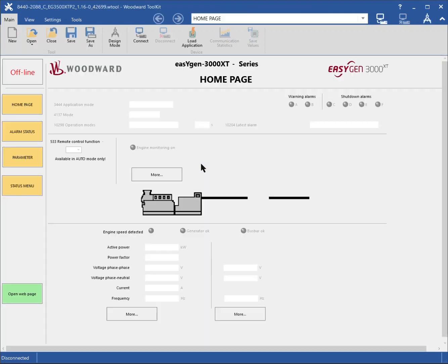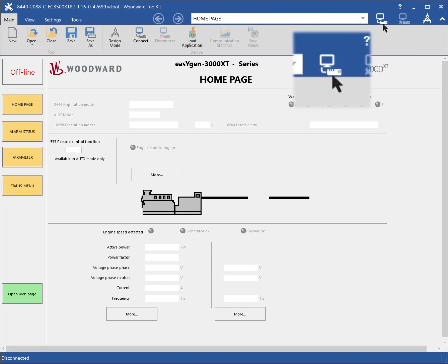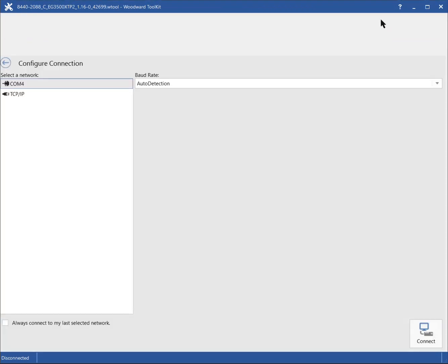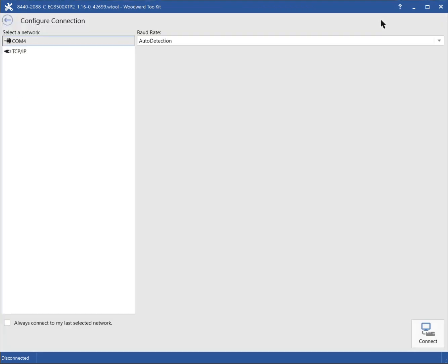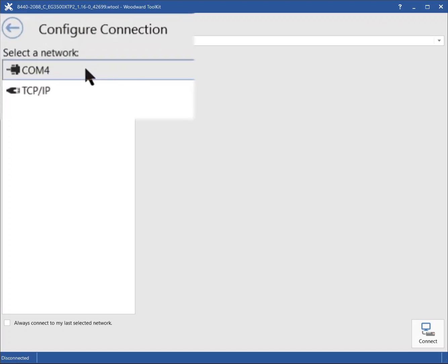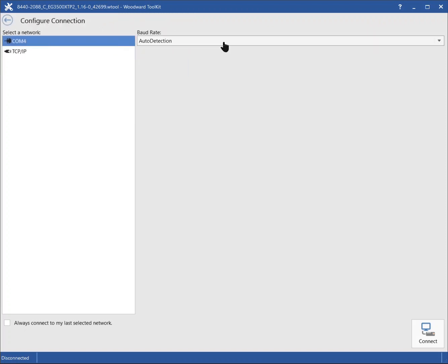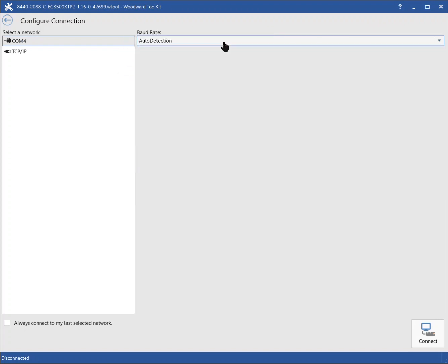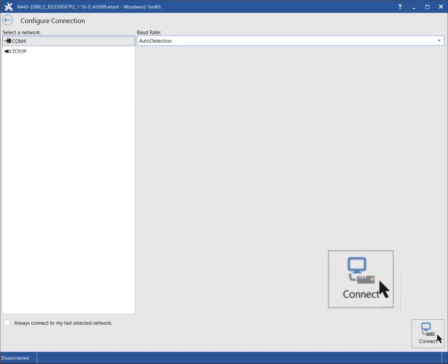Now we can connect to the EasyGen. Click the connect button on top right side of the window. Here you can select which interface to use for the connection to the EasyGen. Select COM4. Leave the baud rate for auto detection. Then click the connect button on the bottom right side.